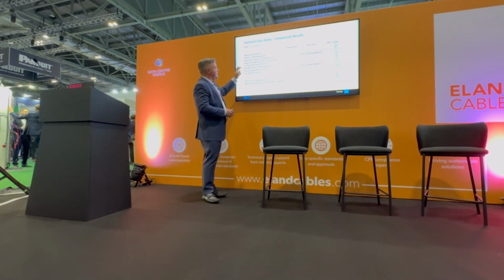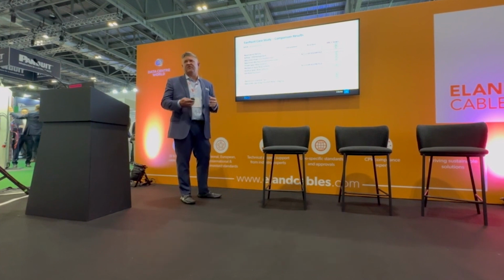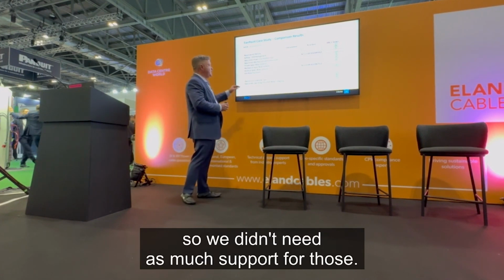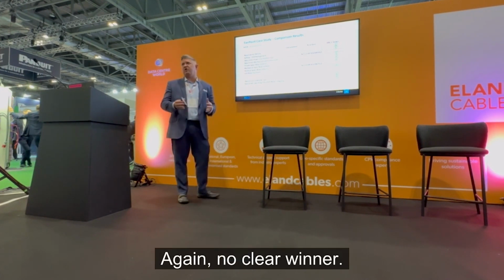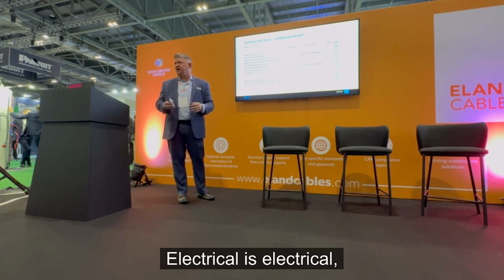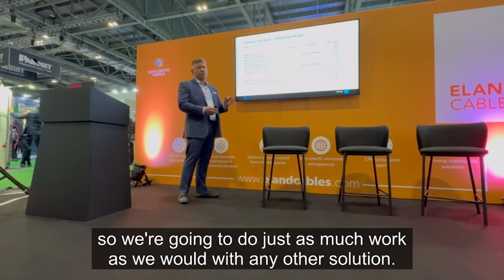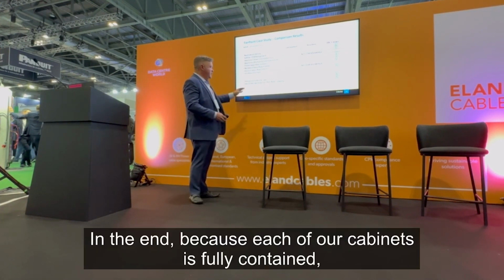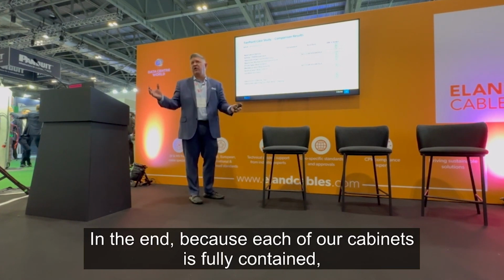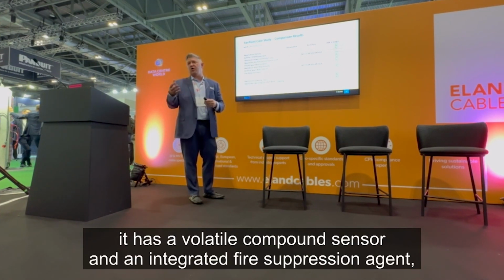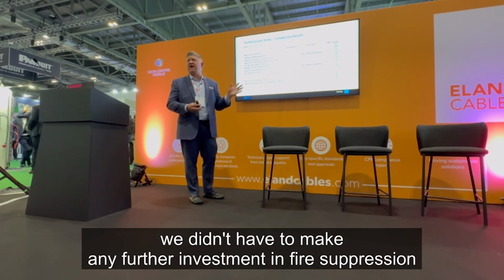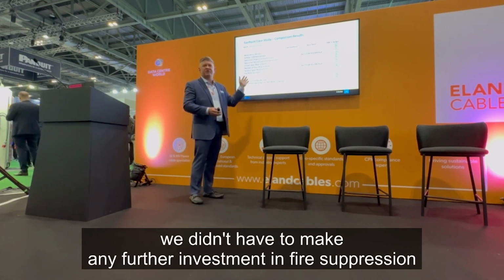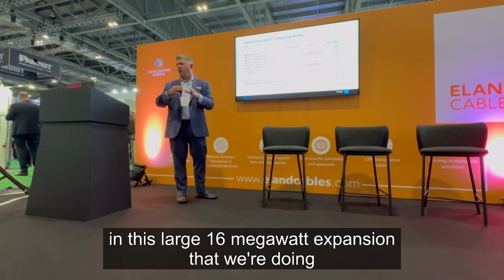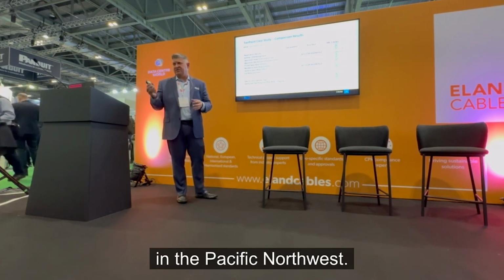For mechanical space, we were able to remove the CRAC units, so less support was needed there. Electrical space, again, no clear winner - electrical is electrical, so we do just as much work as any other solution. In the end, because each of our cabinets is fully contained with a volatile compound sensor and an integrated fire suppression agent, we didn't have to make any further investment in fire suppression for this large 16 megawatt expansion they were doing in the Pacific Northwest.